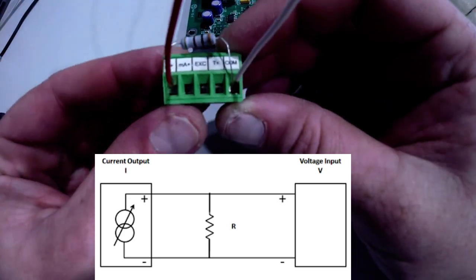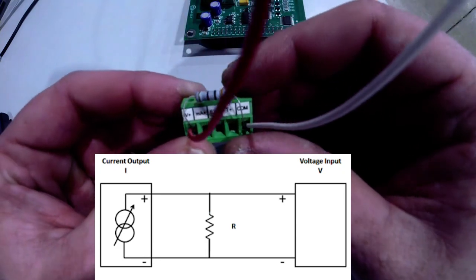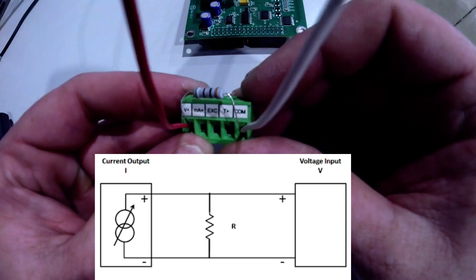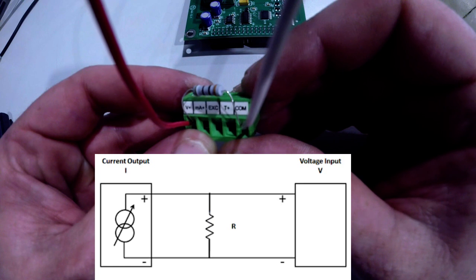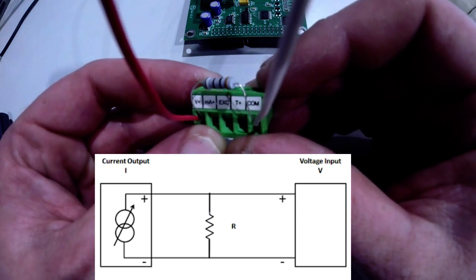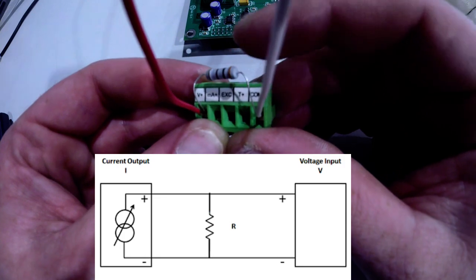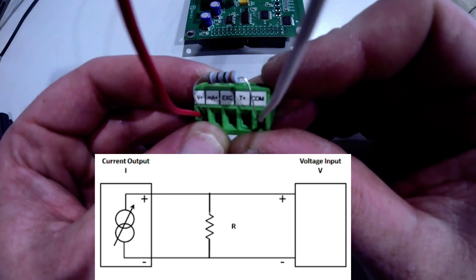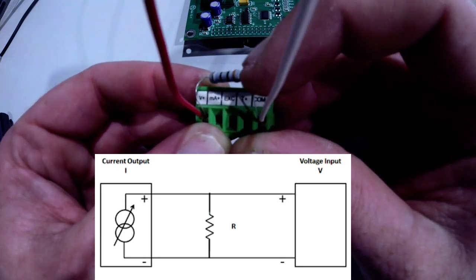And there we have it. With a single resistor and a 0 to 20 milliamp output, we can change our output from 0 to 20 milliamps to 0 to 10 volts DC with the 500 ohm resistor.